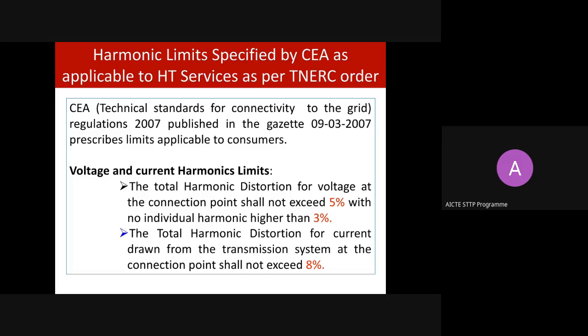Here, what is the limit? What is the harmonic limit? The Central Electricity Authority has the Technical Standards for Connectivity to the Grid Regulations, 2007. They fixed the voltage and current harmonic limits. Total harmonic distortion for voltage at the connection point should not exceed 5%, and no individual harmonic should exceed 3%. The individual harmonic should be less than 3%, and total THD should be less than 5%.